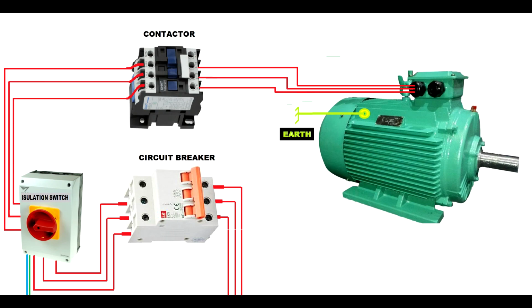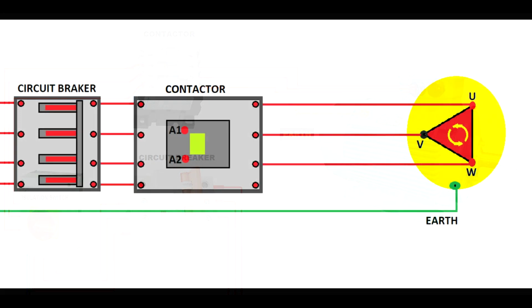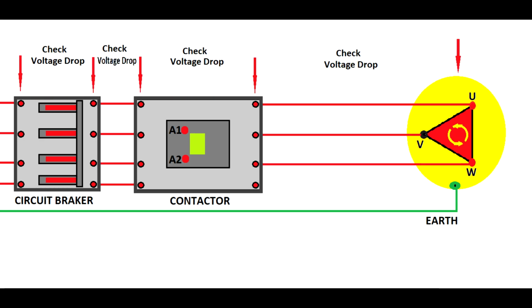So this arrangement is not very good. You see, you have a circuit breaker, you have an isolating switch, a contactor and the motor. I don't like the system, but if you cut corners and do a cheap job, the customer will suffer. Let's see deeper what can happen in this situation. You can have a voltage drop in any of the three phases, and that will happen because of a loose connection or damaged blades inside the contactor.